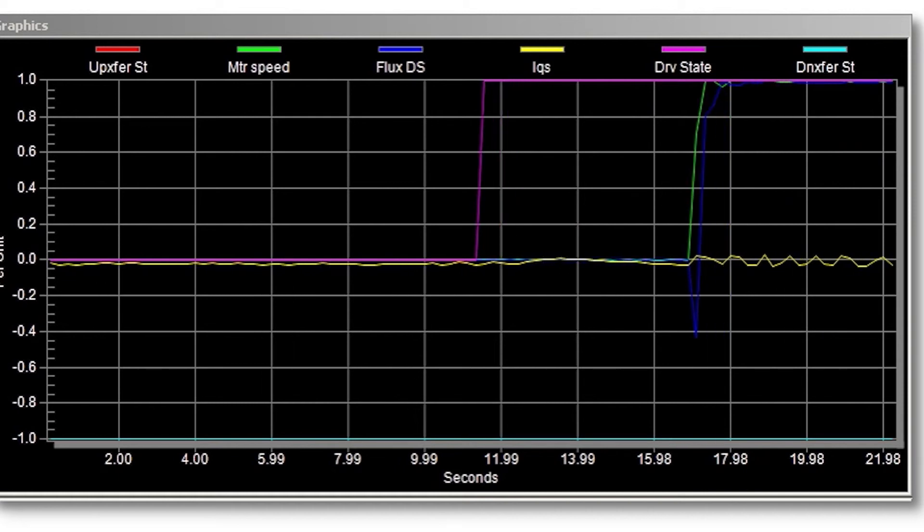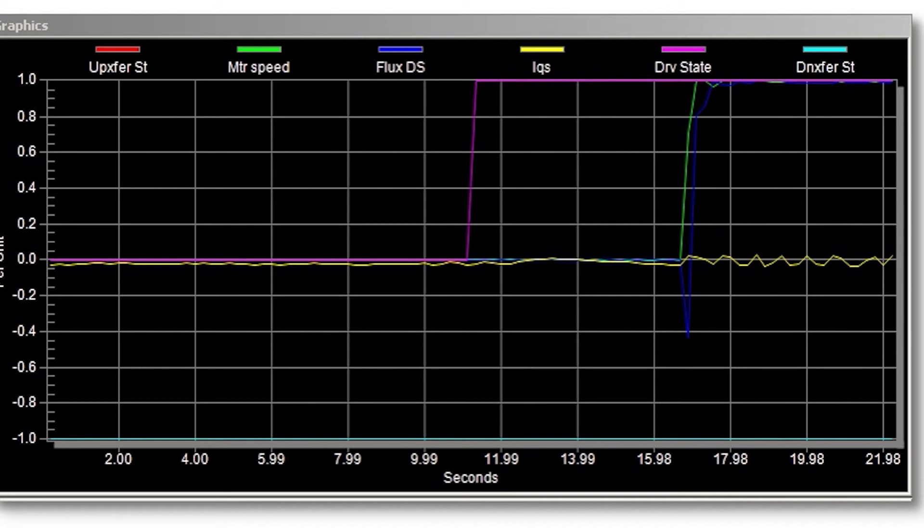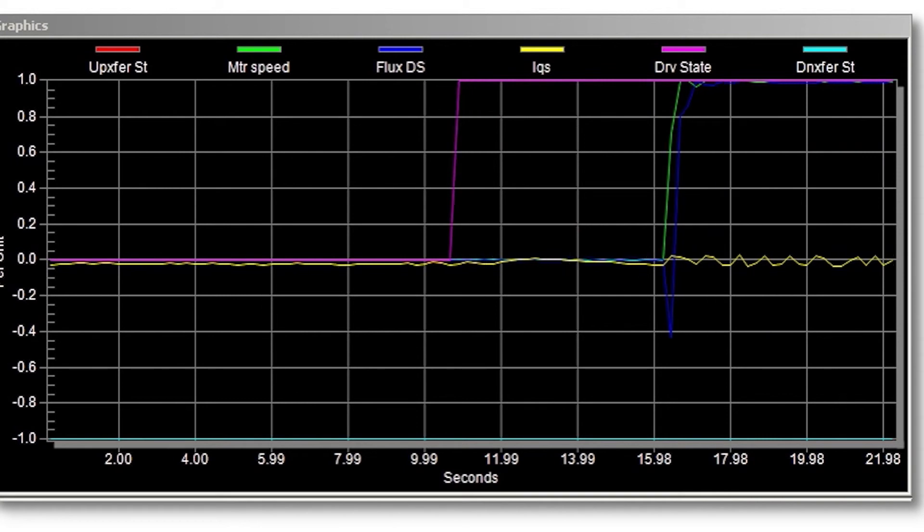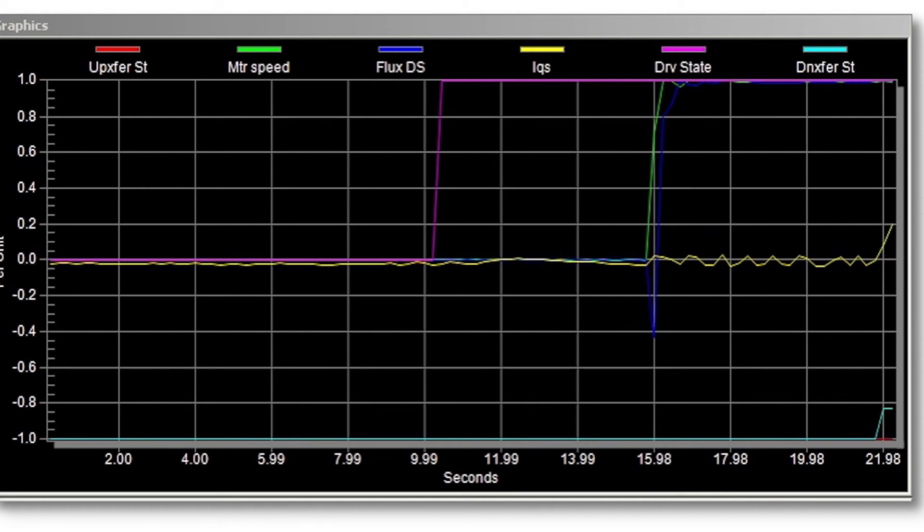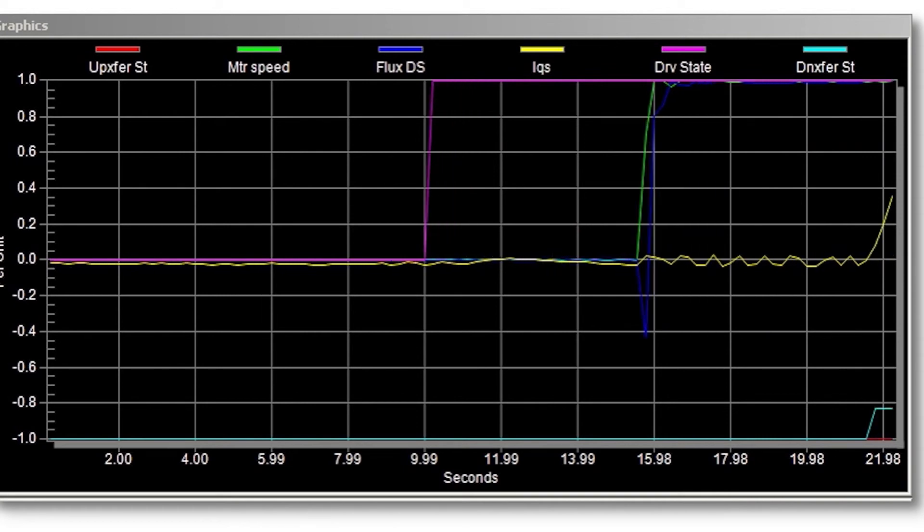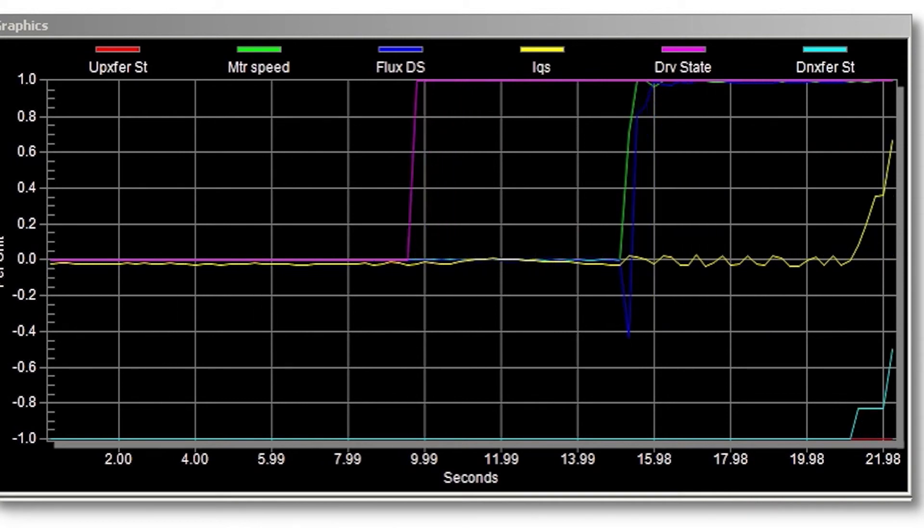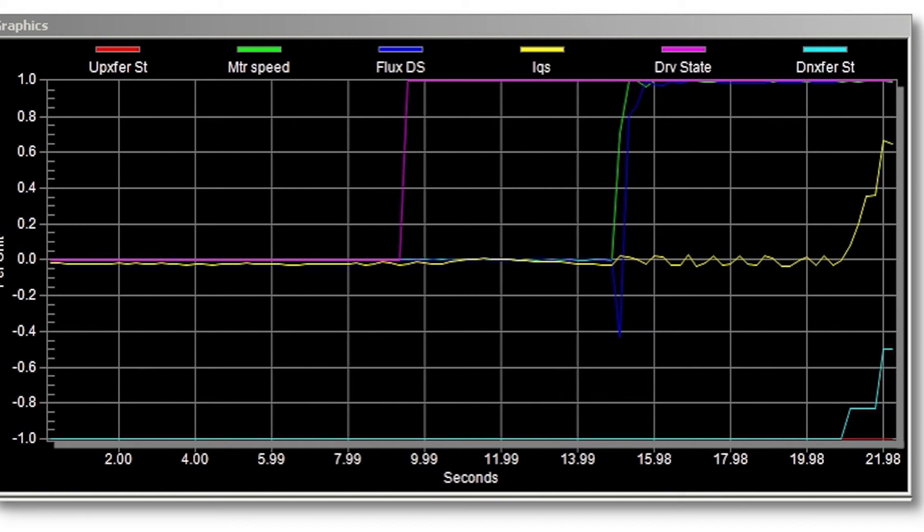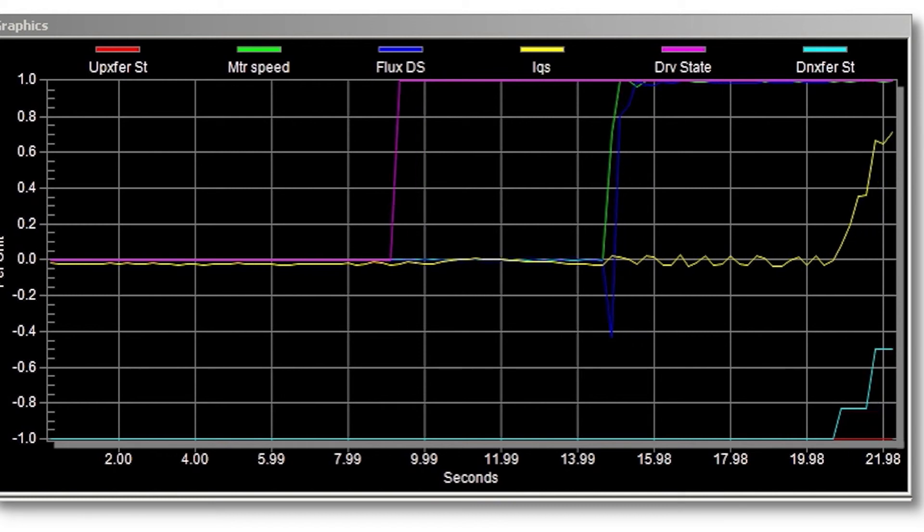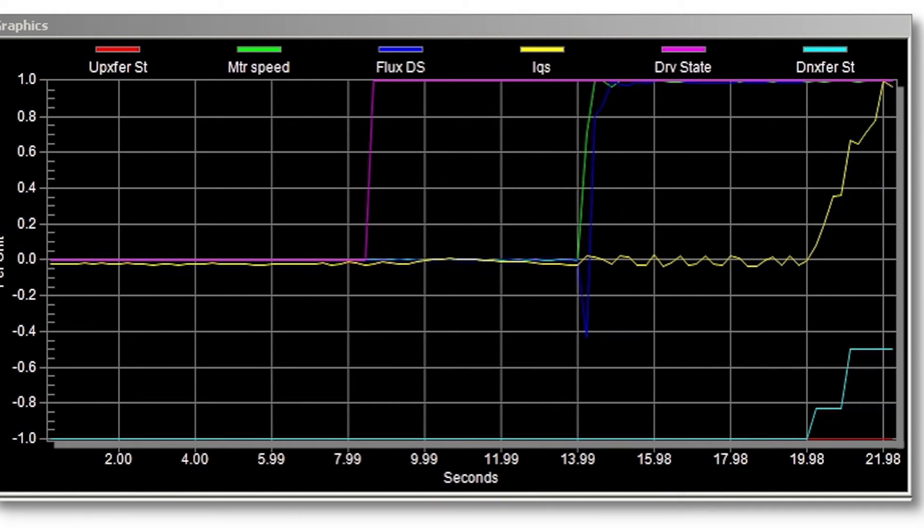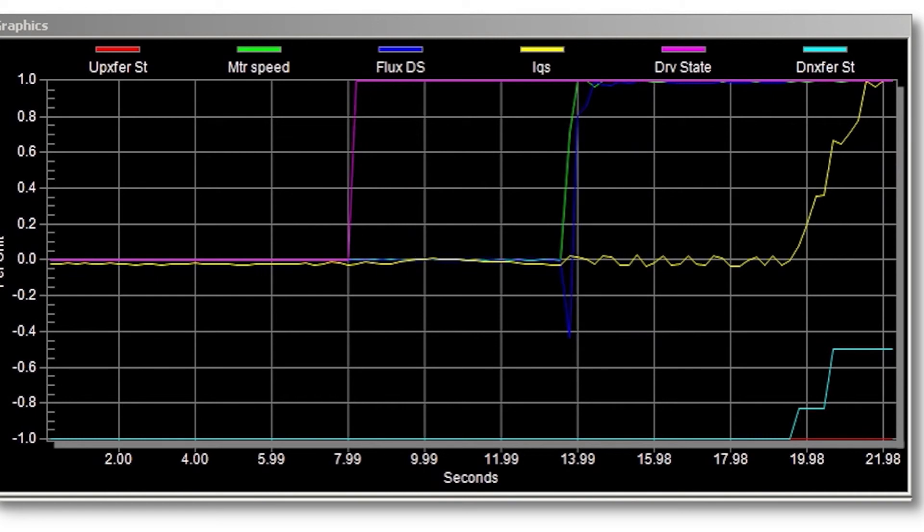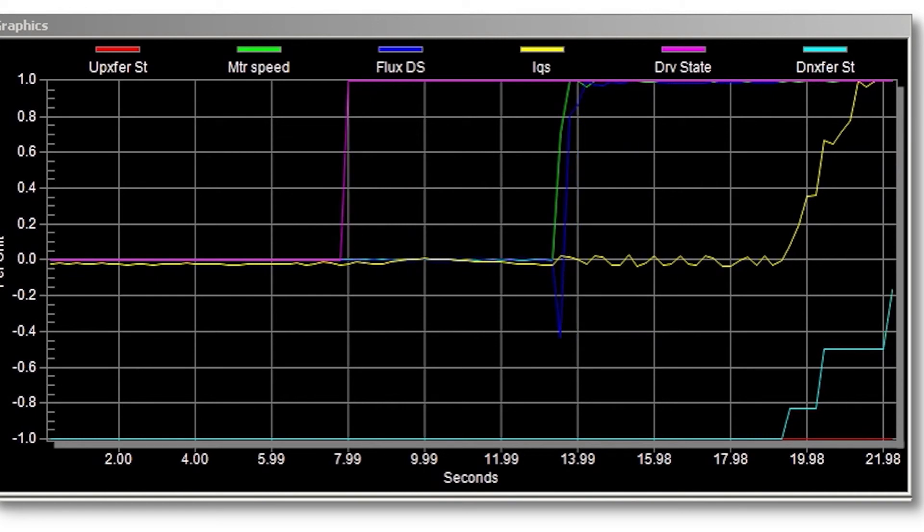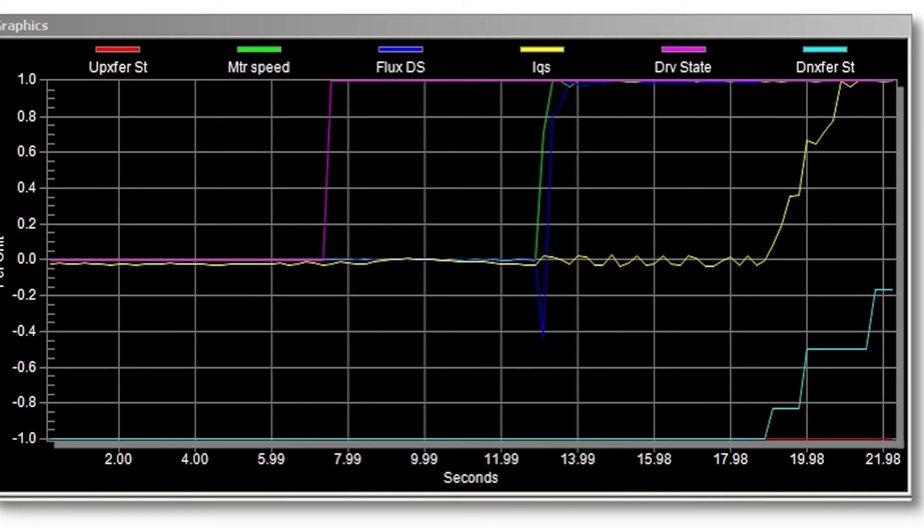Once synchronization is achieved, a request to close the line contactor is generated. The line contactor closes and is acknowledged. At this point, the VFD begins to take control of the motor as seen by the generation of torque in the yellow trace.